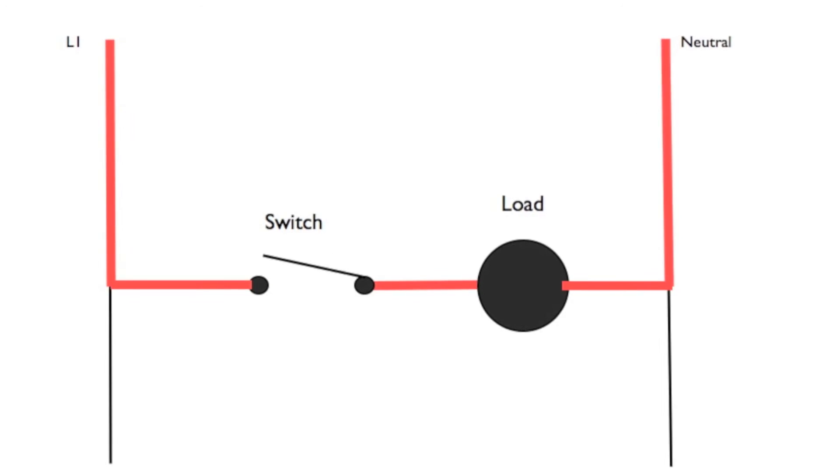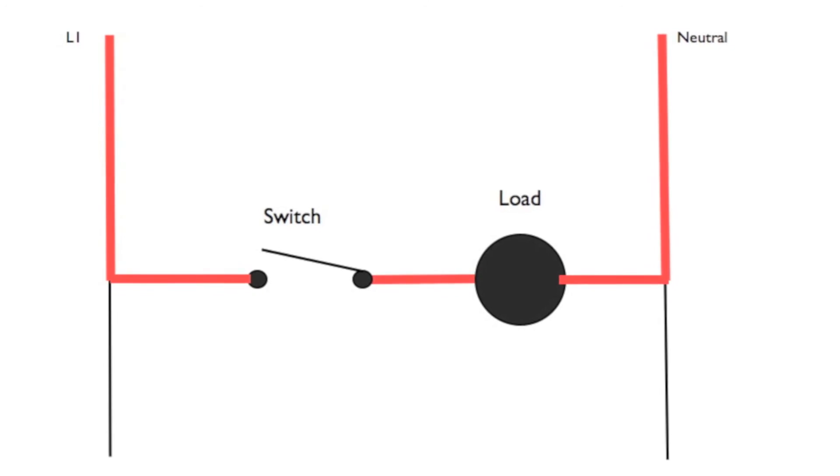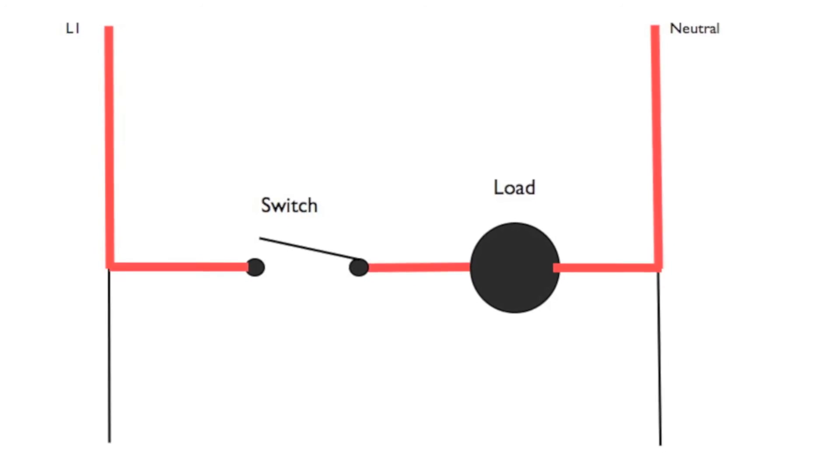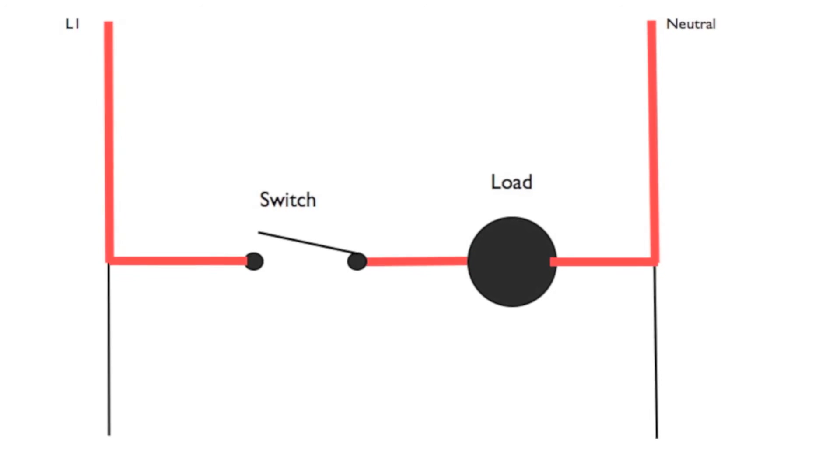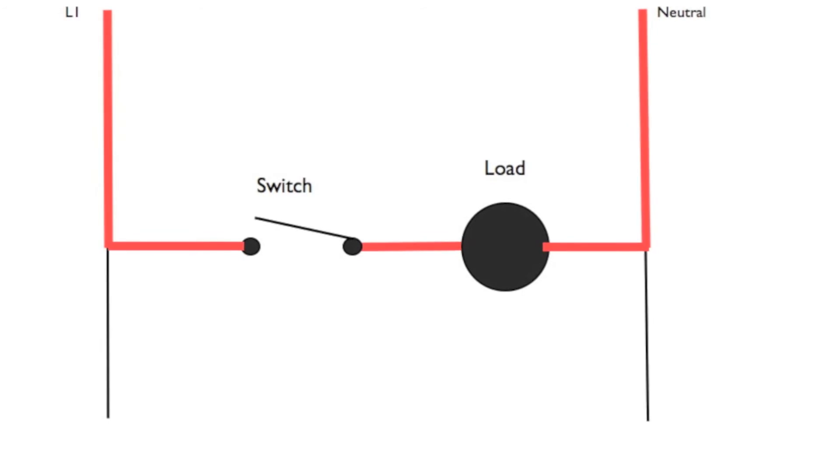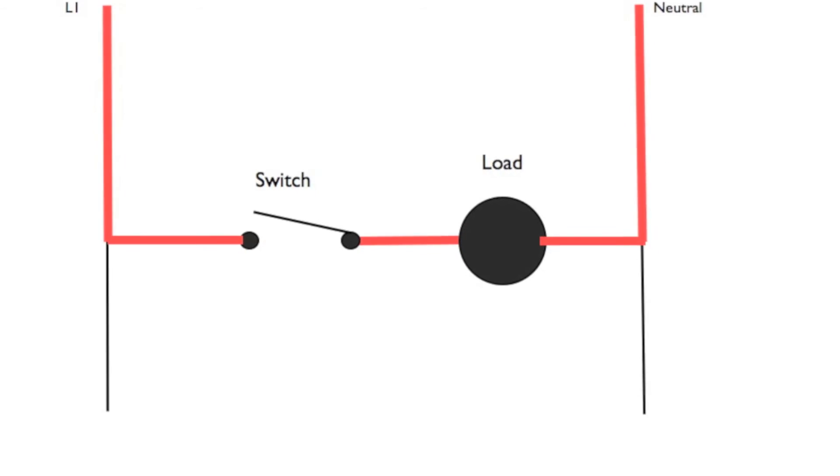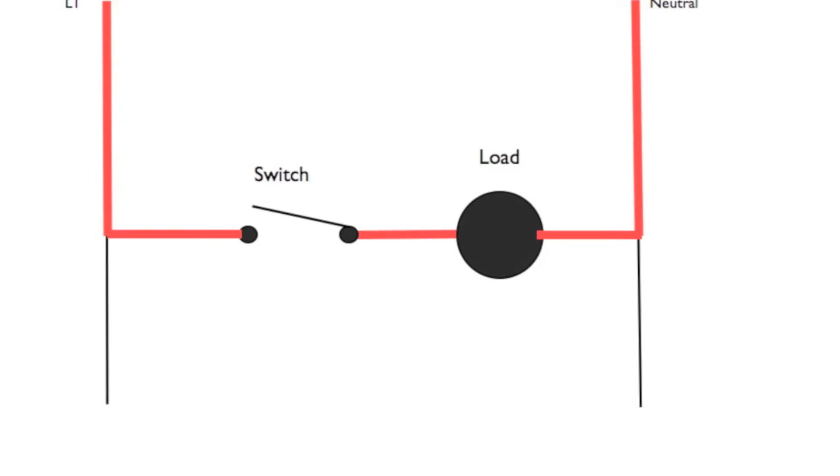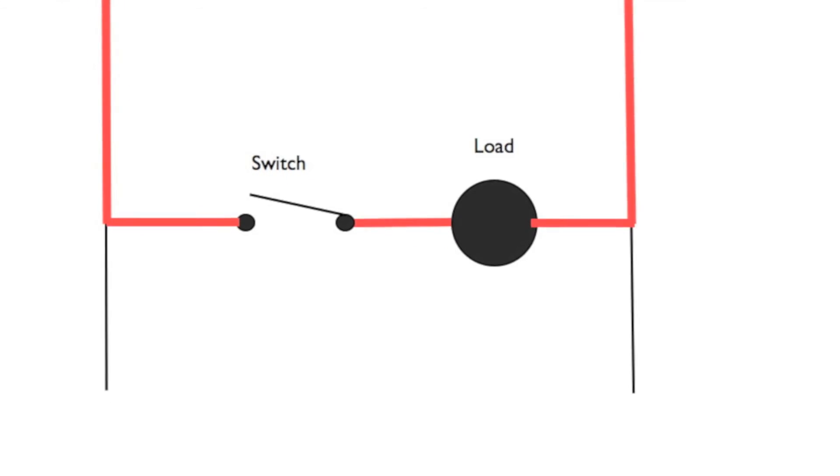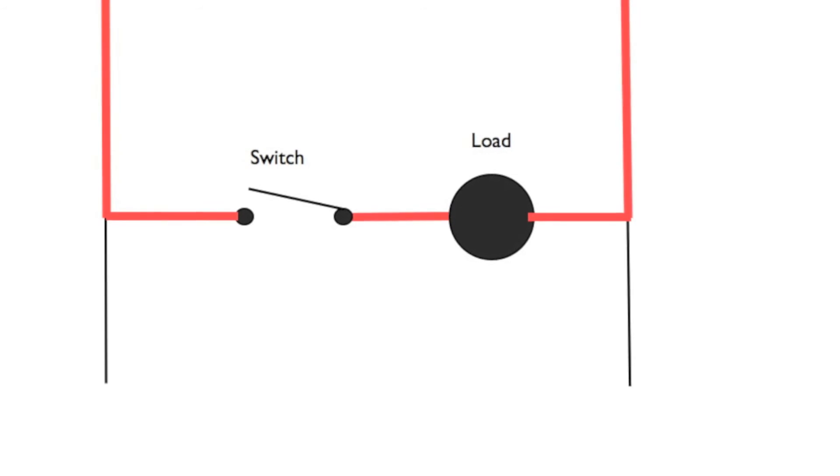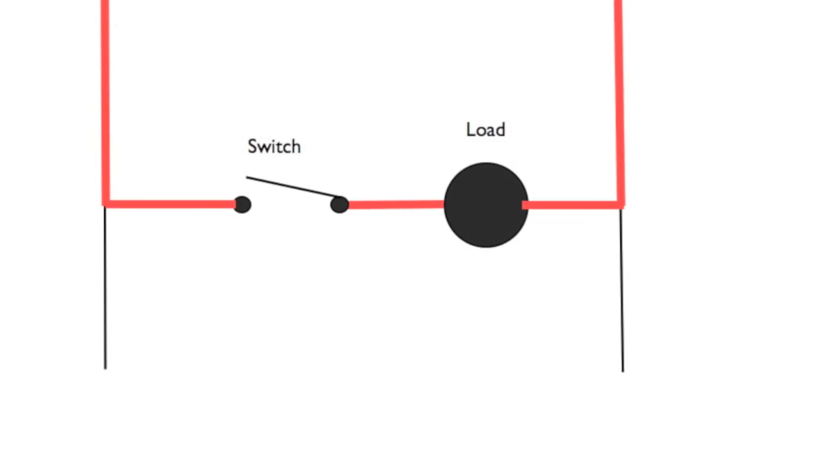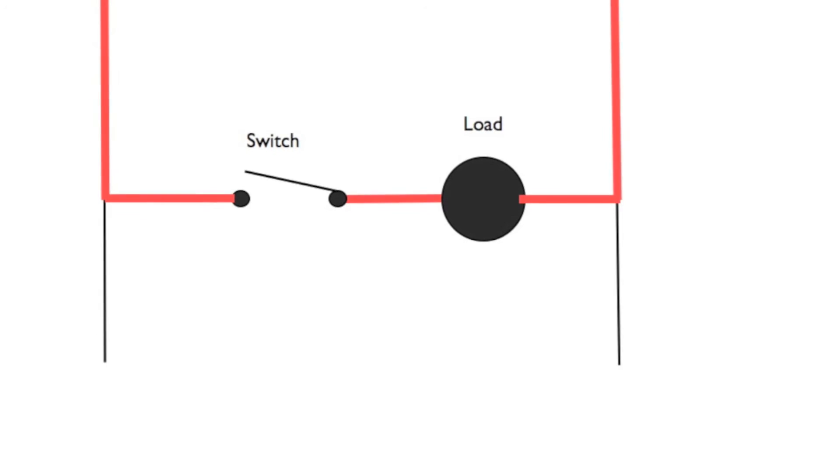Okay, now I'm showing where the power is available. If you look on the left side from L1, power is available right down to the switch. And you look on the right side, power is available down the neutral through the load and up to the switch. So the only thing that is keeping this circuit from operating is the open switch.